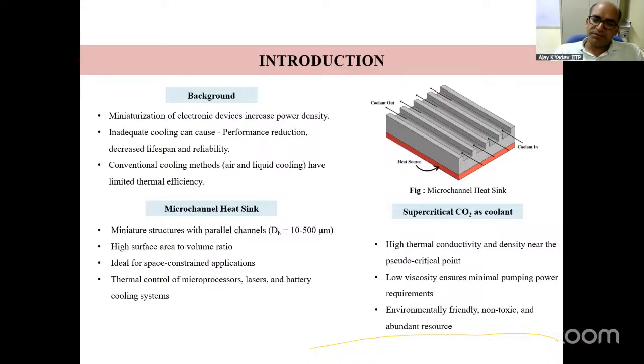With microchannels, the surface area to volume ratio increases. Since heat transfer depends on area, H A delta T, if area is more, heat transfer will be more. So we are increasing the area by putting small microchannels - this is the advantage.